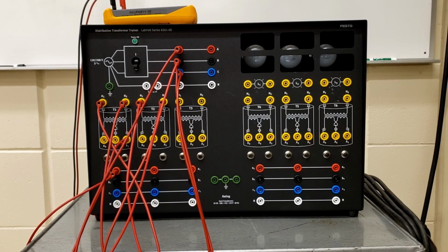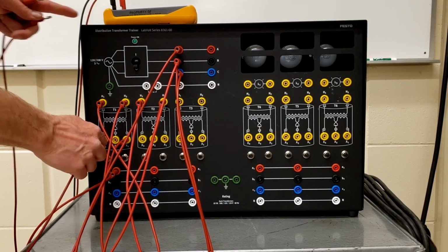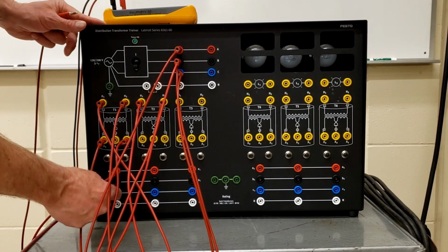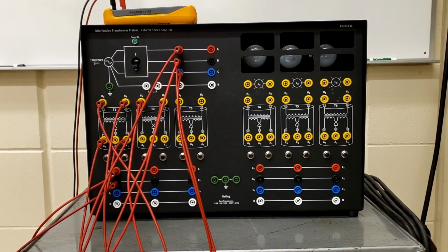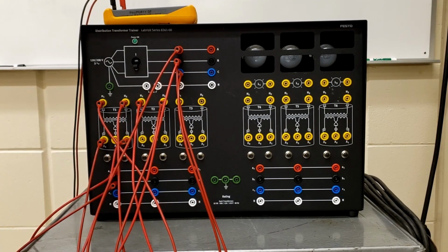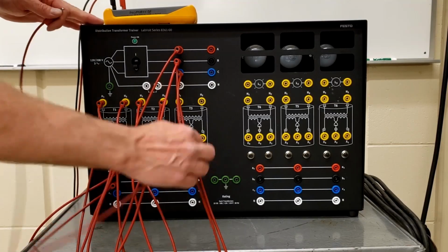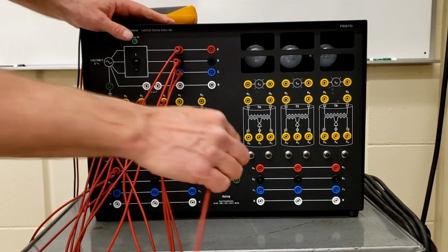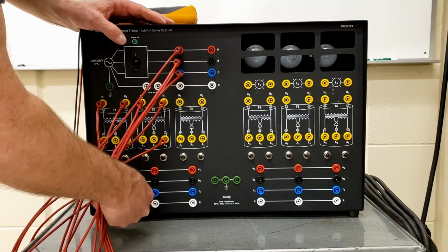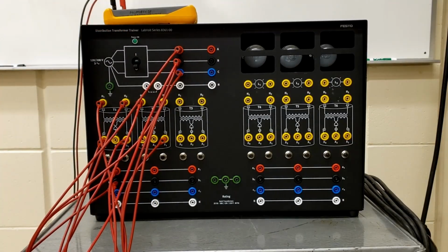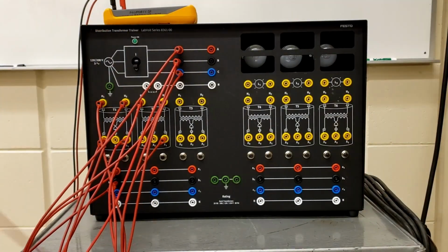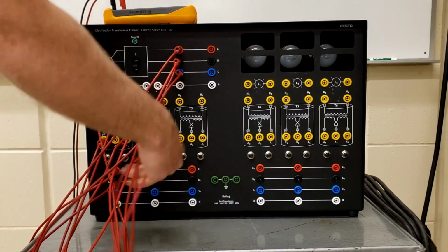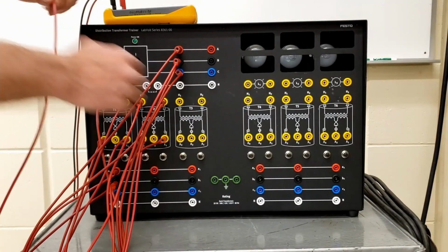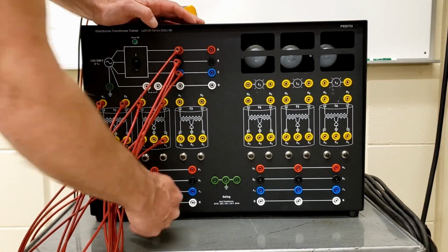And then X3 is going to go to B. So again we got A to B, this guy is going to feed B phase. So A to B, and then it should be B to C. Remember that these guys are backwards, so now X1 is going to go to B. So X1 of this second transformer is going to feed B. And then we got X3 that's going to feed C. So X3 of this guy is then going to feed the C phase.